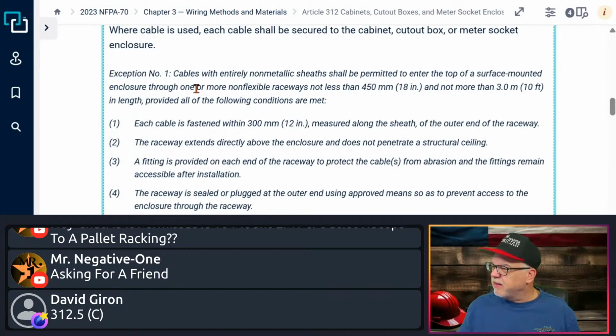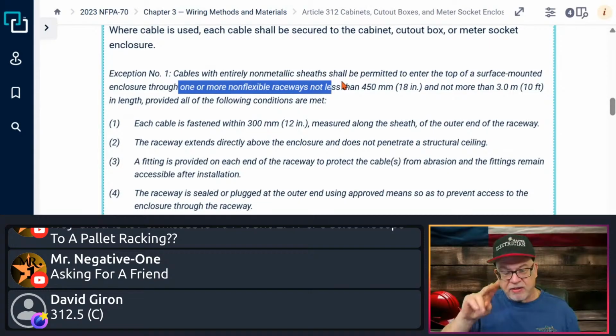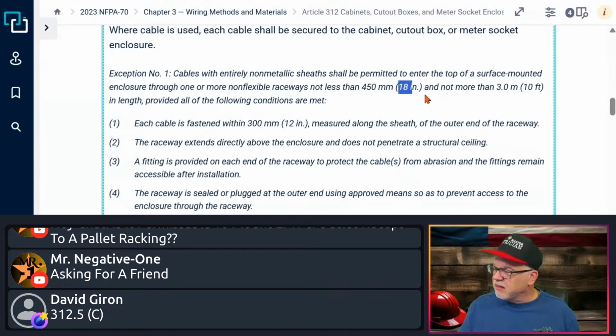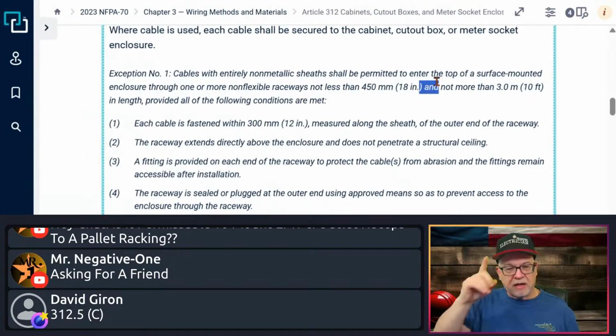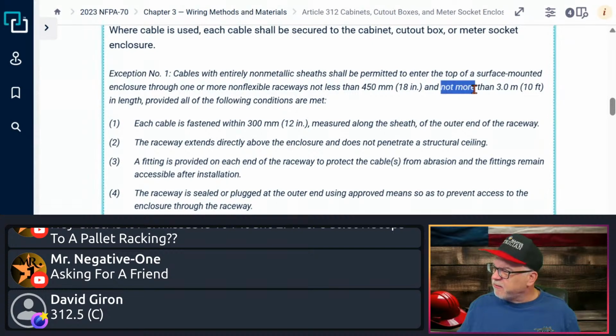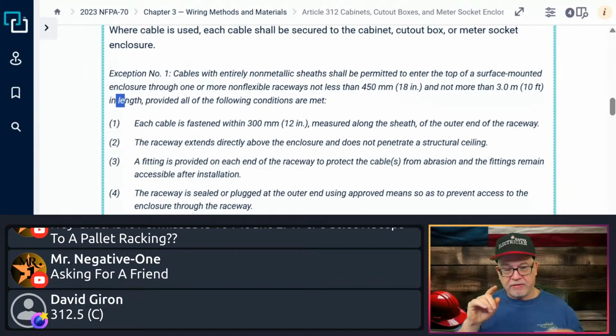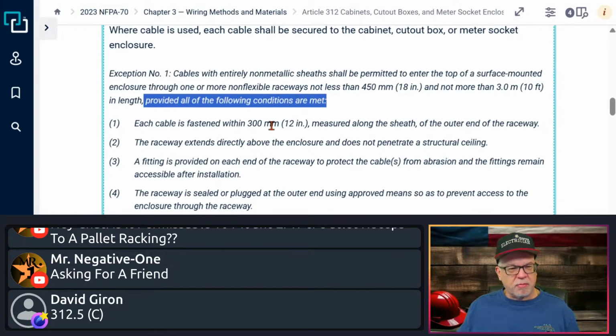All right. Next, through one or more non-flexible raceways, not less than, second fact, not less than 18 inches. Second requirement. Third, and means it's got to include this and that. It's not an or. And not more than 10 feet in length. So the raceway that these cables come into, through the top, it's got to be at least 18 inches, not more than 10 feet, okay? Provided all of the following conditions are met.